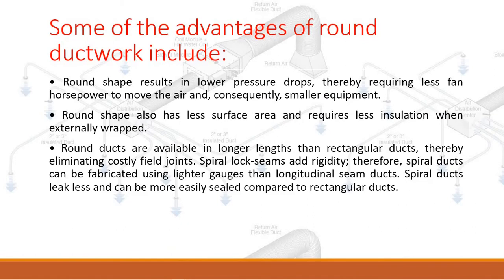Advantages of round ductwork include: round shape results in lower pressure drops, requiring less fan horsepower to move the air and consequently smaller equipment. Round shape also has less surface area and requires less insulation when externally wrapped. Round ducts are available in longer lengths than rectangular ducts, eliminating costly field joints. Spiral lock seams add rigidity, so spiral ducts can be fabricated using lighter gauges than longitudinal seam ducts. Spiral ducts leak less and can be more easily sealed compared to rectangular ducts.